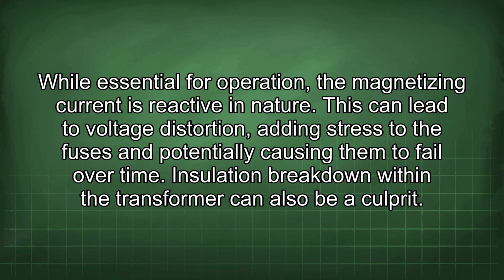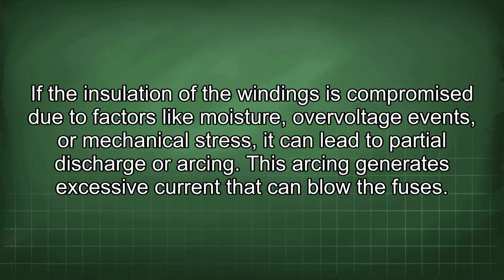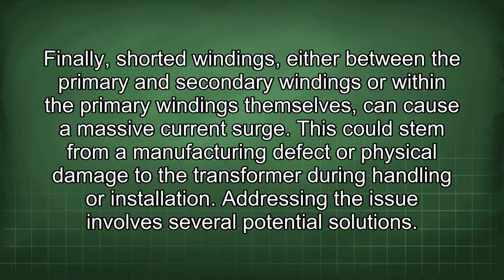Insulation breakdown within the transformer can also be a culprit. If the insulation of the windings is compromised due to factors like moisture, overvoltage events, or mechanical stress, it can lead to partial discharge or arcing. This arcing generates excessive current that can blow the fuses. Finally, shorted windings, either between the primary and secondary windings or within the primary windings themselves, can cause a massive current surge. This could stem from a manufacturing defect or physical damage to the transformer during handling or installation.